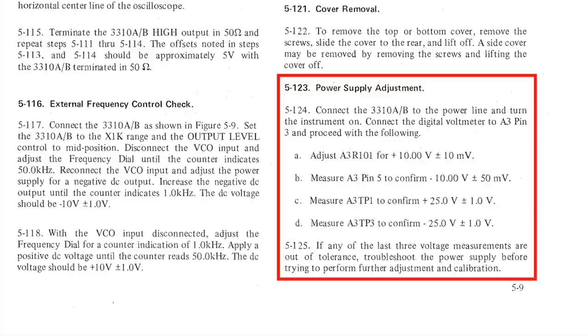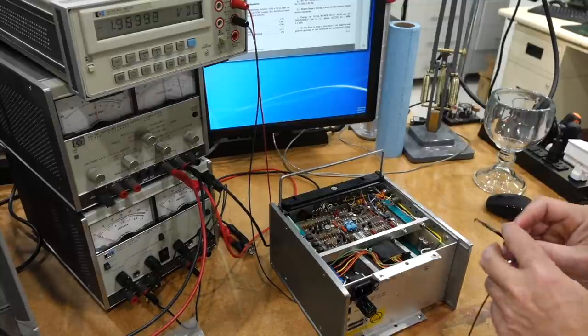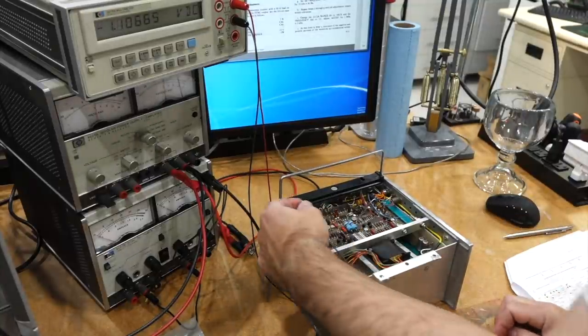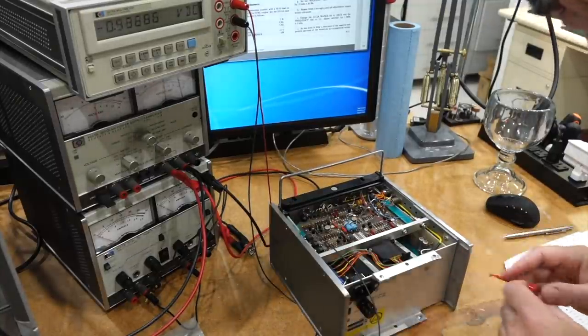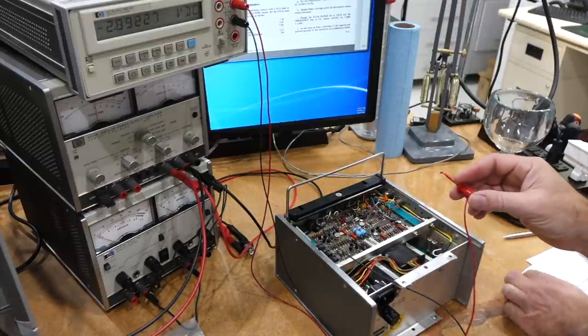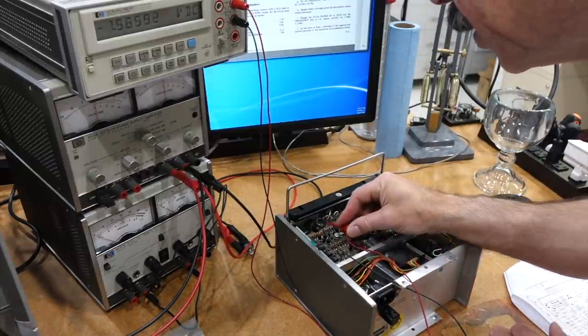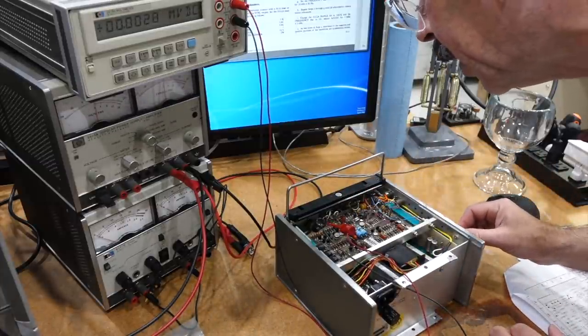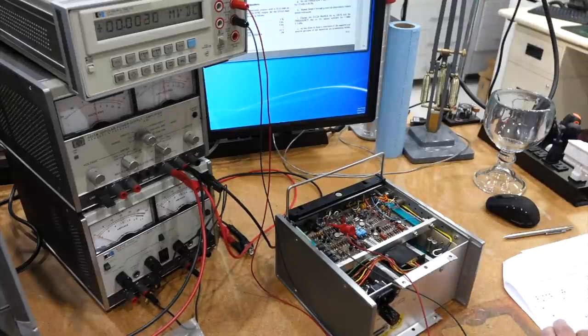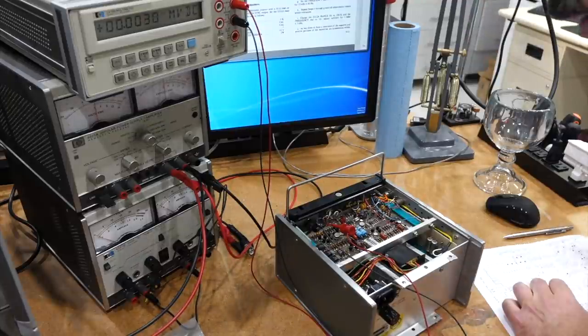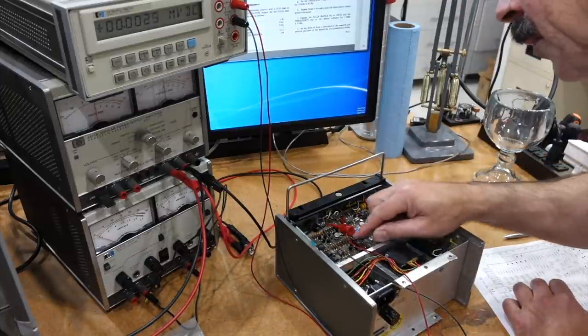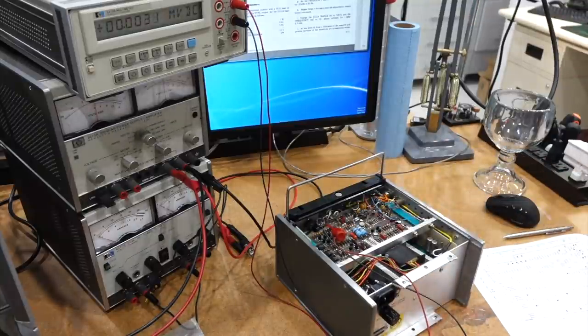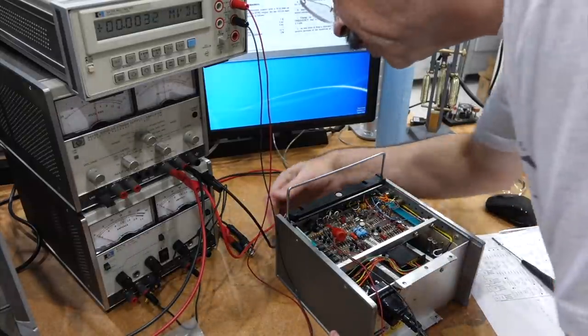The pot is accessible through the bottom of the instrument. And they label everything, so it makes it really simple. So this is ground, plus 10 volts, right? That's what we do. You just do one adjustment and it adjusts everything. And the 10 volt adjust is this fellow over here, written on it. Okay, so on we go.